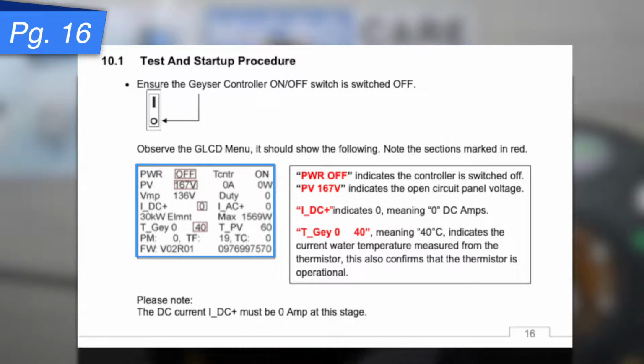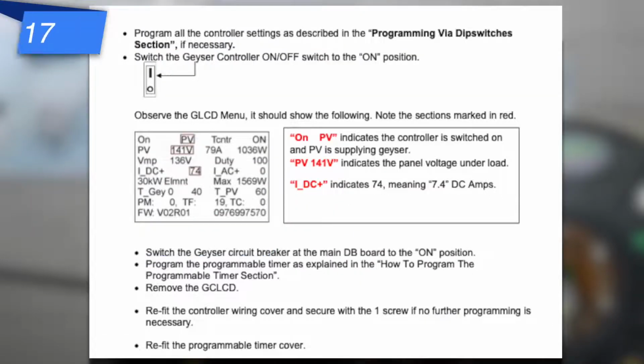Number one, power off. Secondly, PV, 167 volts. That indicates the open circuit panel voltage. IDC plus indicates 0. That means there's no DC amps coming through, which is correct. And then we're looking for temperature. You should be picking up temperature now from the thermistor, which we showed you how to install. It'll say something like TGEY 0 and then a gap and then the temperature. In this case, I've indicated 40 degrees. You should be picking that up at this point before we've even switched on. Please just note there, the DC current must be 0 amps at this stage. Very, very important.